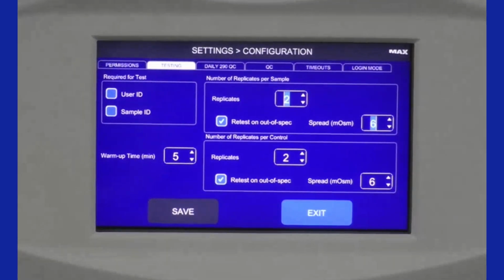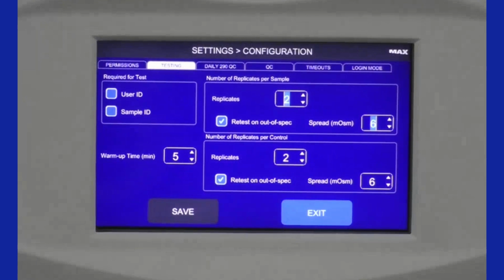But if we go into testing, you can see that over here, you can decide if a user ID or a sample ID is required for the test. You can designate the number of replicates per sample. So that top box where it says number of replicates per sample is actually how many replicates the instrument will automatically run on your patient samples. So if you're a laboratory that likes to run just one test per sample, that's totally fine. You can bring it down to 1. If you like to run 2, that's fine too. You can bring it up to 2. You can do all the way up to 5 if you really wanted to, and if you had enough sample.